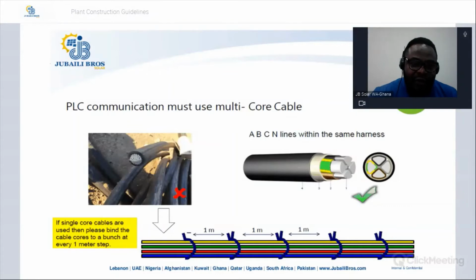Again, as I mentioned earlier, if you're going to use PLC communication, our first suggestion is for you to use a multi-core system. Okay, the multi-core system is the best. If for whatever reason you cannot, whether it's affordability or any other technical reason, you prefer single core systems, then you have to bundle them at every 1 meter along their way. And that's going to be difficult. But yes, if you have single core systems, then you will have to make sure that you group all the cores together.